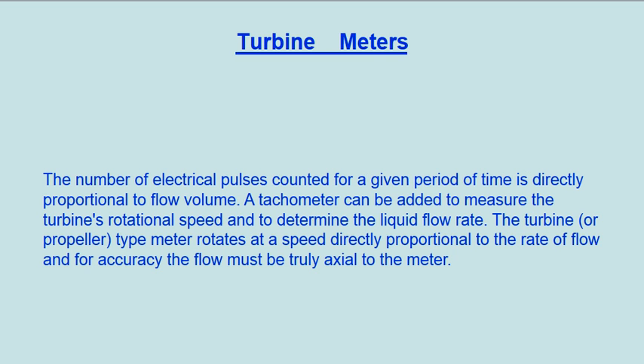A tachometer can be added to measure the turbine's rotational speed and to determine the liquid flow rate. The turbine, or propeller, type meter rotates at a speed directly proportional to the rate of flow, and for accuracy the flow must be truly axial to the meter.